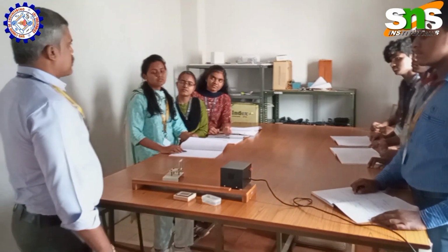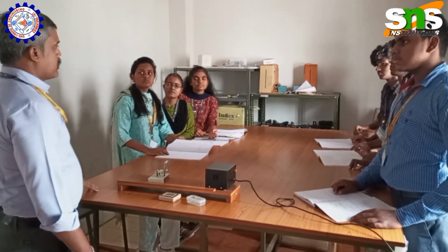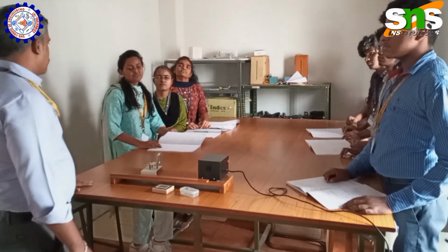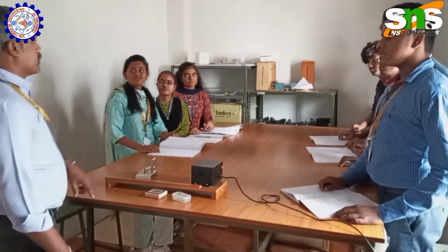If we change the laser, will anything change? Yes, definitely, because the output changes. The particle size and the diffraction pattern will be obtained with more brightness. Sometimes the particle may be affected, and we do not get proper readings. So we use it only for lower efficiency experimental verifications, especially of particle size. We do not use it on any biological samples, because the laser affects biological samples.